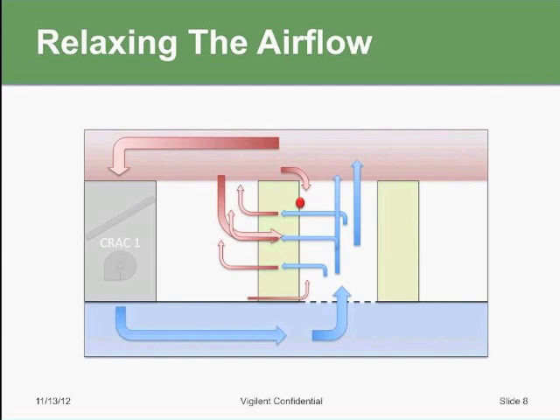And so what is the solution when a facility operator has hotspots? Well, they say, well, I'm not redundant enough. I need more cooling capacity. And so the solution is to install more cooling capacity. And of course, if you install more cooling capacity, you're just increasing the airflow in the facility, and an excess amount of airflow in the facility causes more mixing, which leads to more hotspots. So in fact, when you think you're increasing the redundancy or installed redundancy of your facility, you're actually making the situation worse.